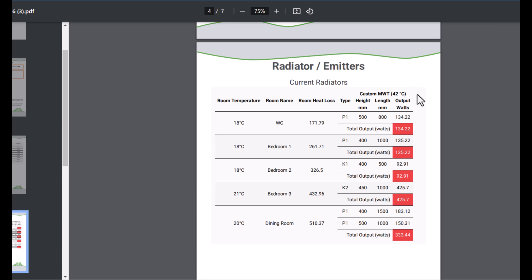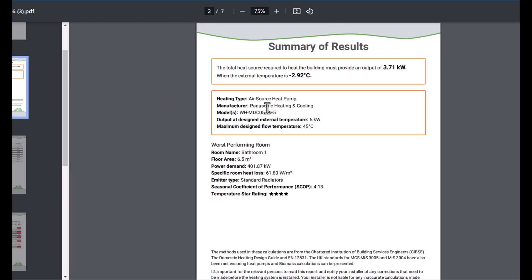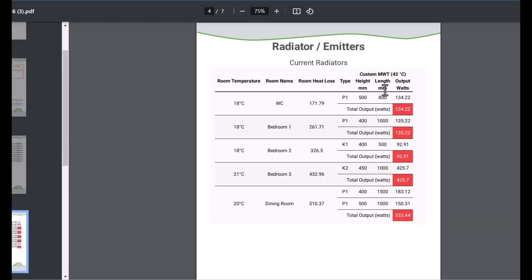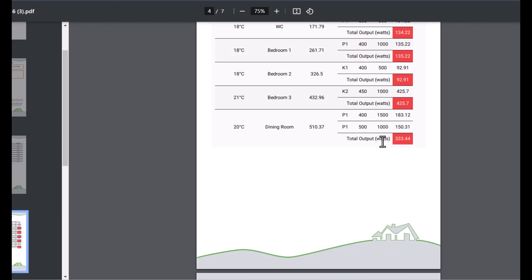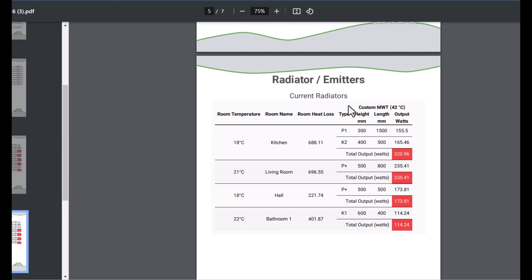What emitters are currently installed and what emitters you're proposing to change out or even leave in as well. So we've got current emitters here. We're using the custom mean water defined temperature as well. You can see that because we've specified a heat pump here with a flow temperature of 45 degrees, then the current emitters aren't suitable for this lower flow temperature and change in Delta T.